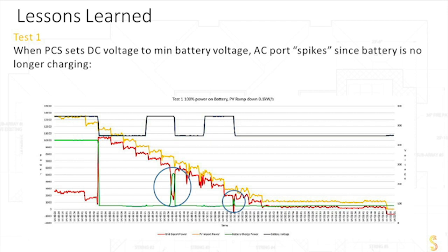This is a demonstration to show that even under worst case scenarios, the inverter will never allow the battery to violate these rules, these NEM compliance rules. And this gives utility companies and regulators great assurances that the system will do what we say it's going to do, even when it's not operating correctly, even when the battery tries to charge too much when it shouldn't. Because the inverter is acting as like the last line of defense. It's the safety mechanism.